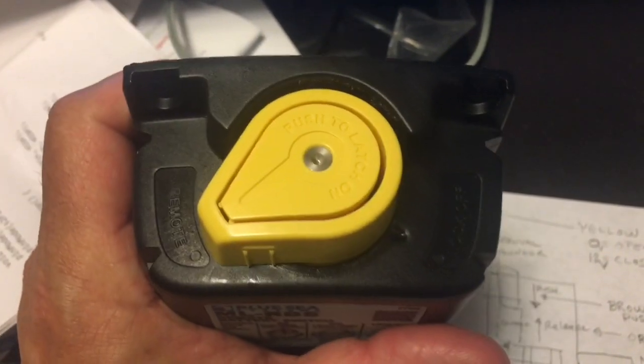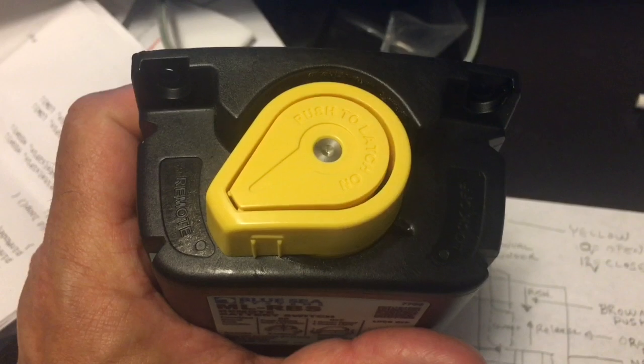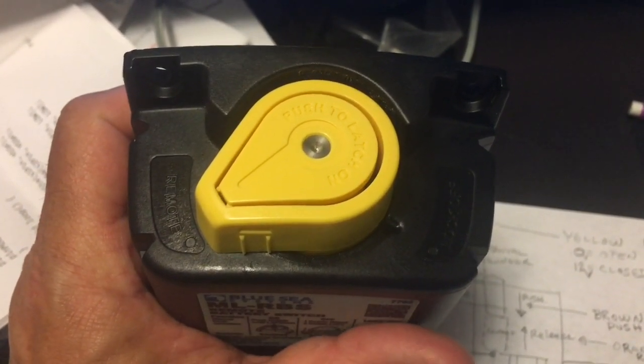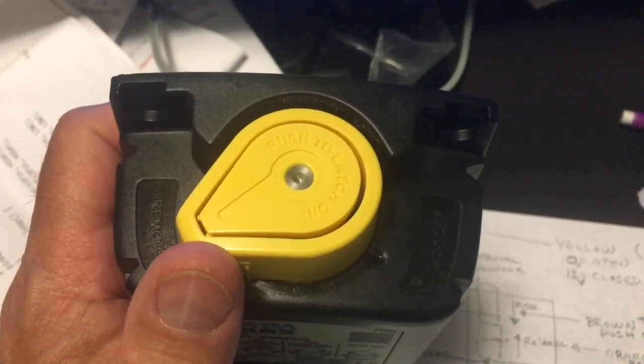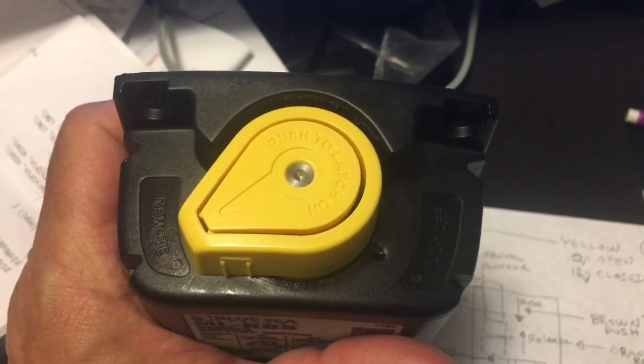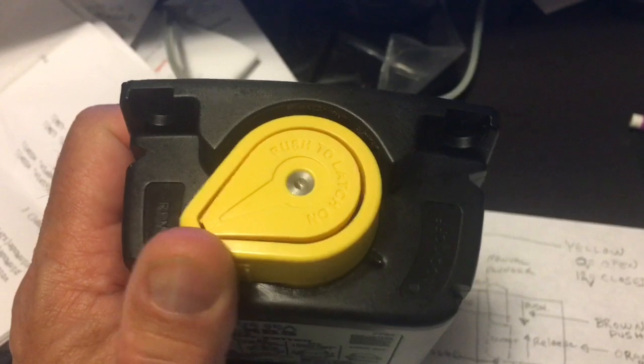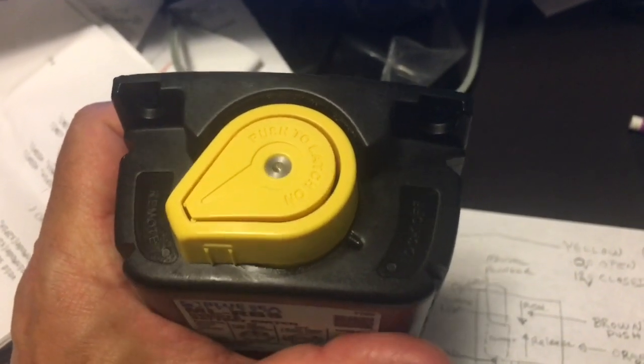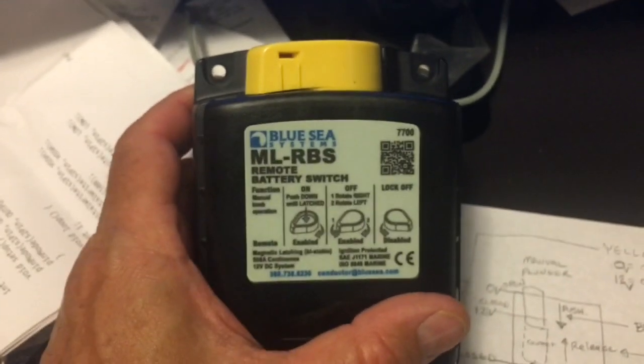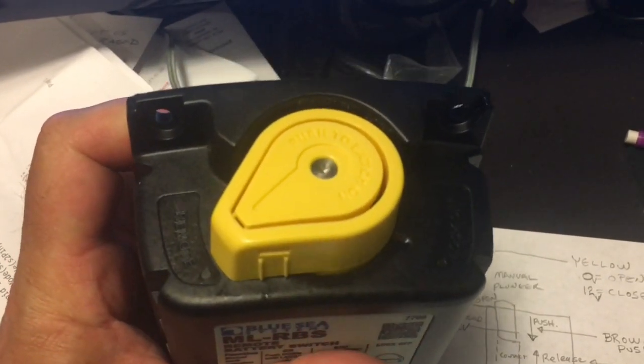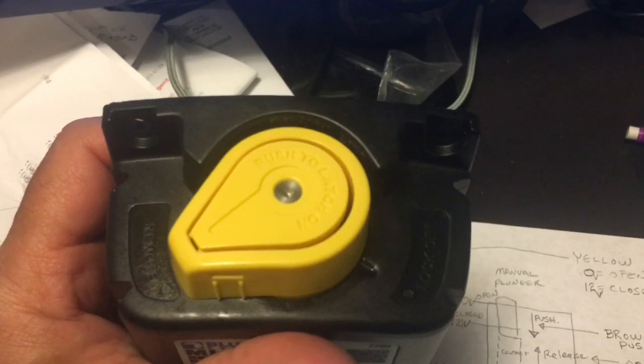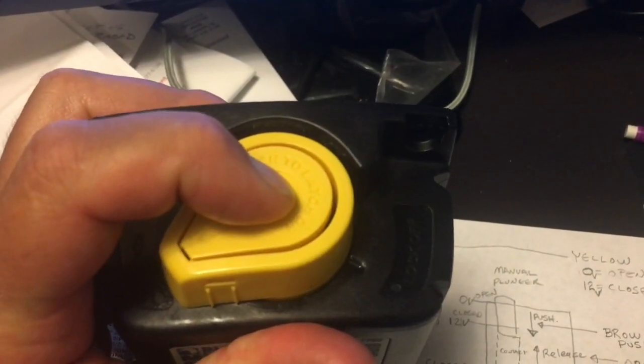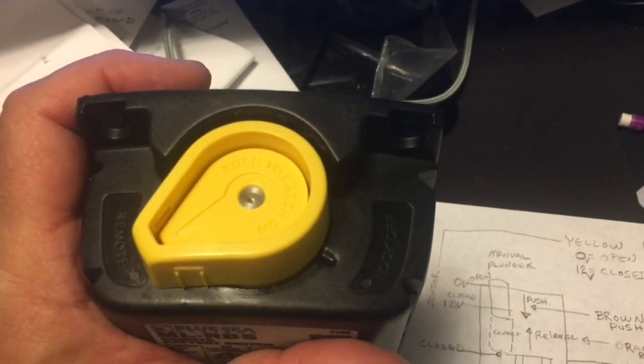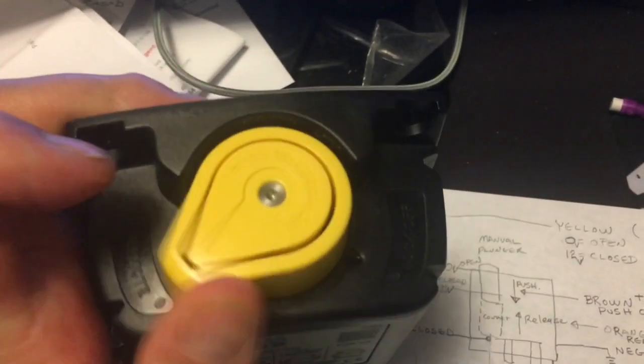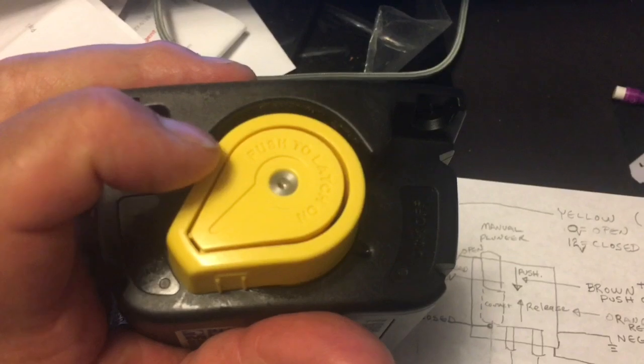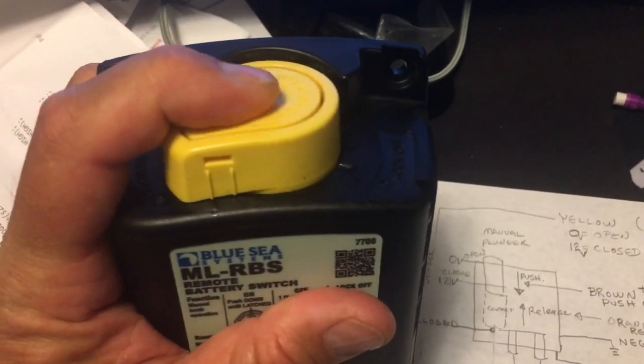This type of relay is a bistable magnetic latching relay. That means if it's in the non-switching state, where it's not opening or closing and it's just in a particular state, it uses no energy at all. So as far as power consumption, this is a great relay. The issue with these relays is you need to pulse them, and that is the problem sometimes. So I'm going to go over that a little bit here. I can show you how the pulsing works with a microprocessor, but that's the general idea. You need to pulse these things to change the state.